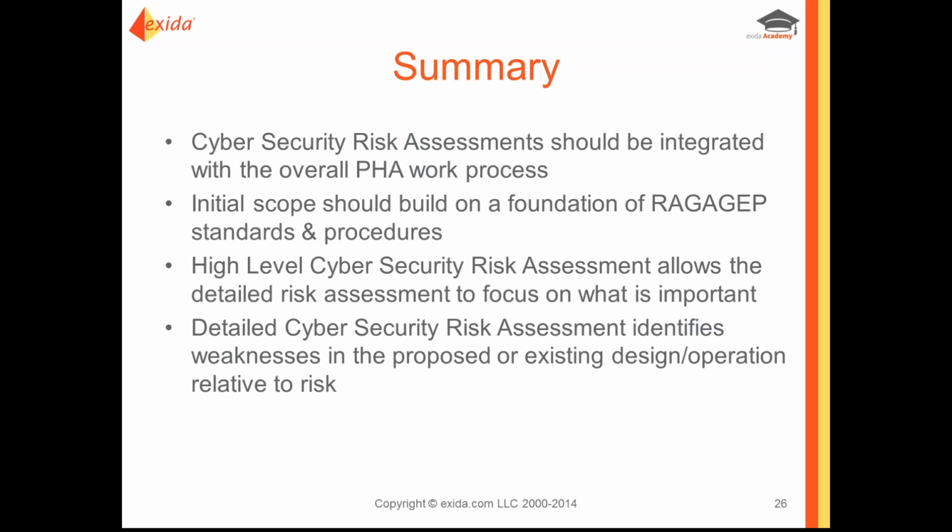A high-level cybersecurity risk assessment allows the detailed risk assessment to focus on what's important. This is the initial assessment of your risks and Paretoing of the risks to determine those that are high, those that are low, less consequence. And the detailed cybersecurity risk assessment identifies weaknesses in the proposed or existing design or operation relative to the risk.